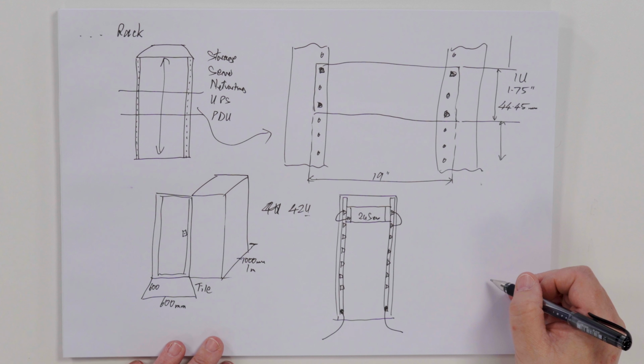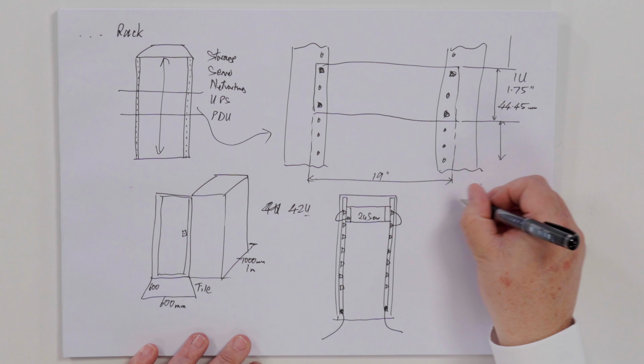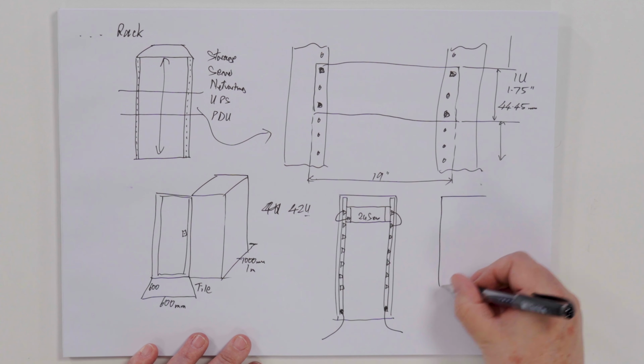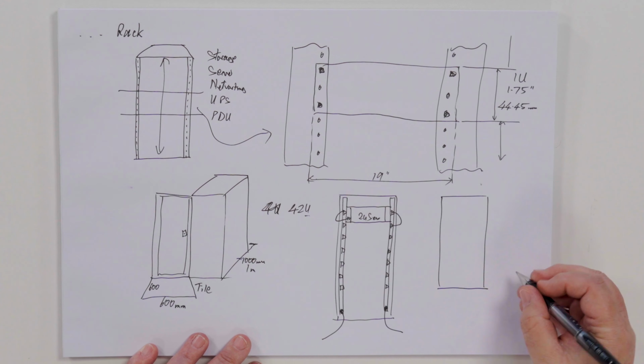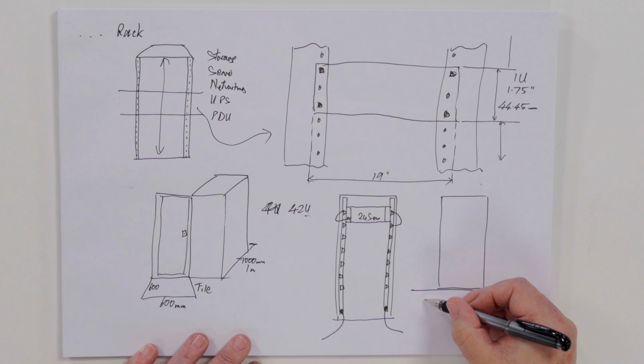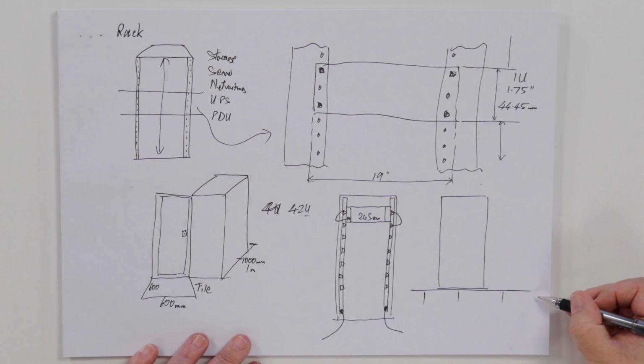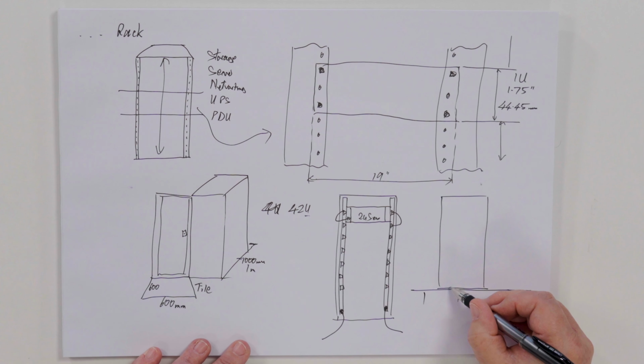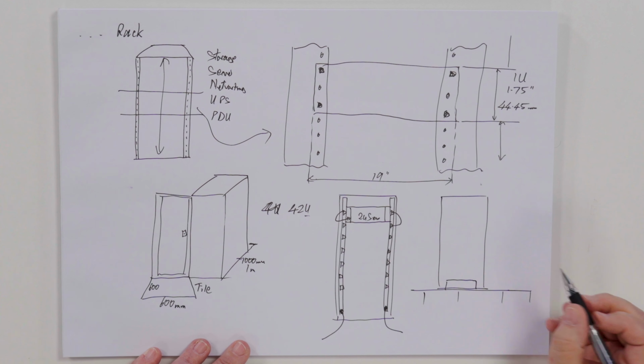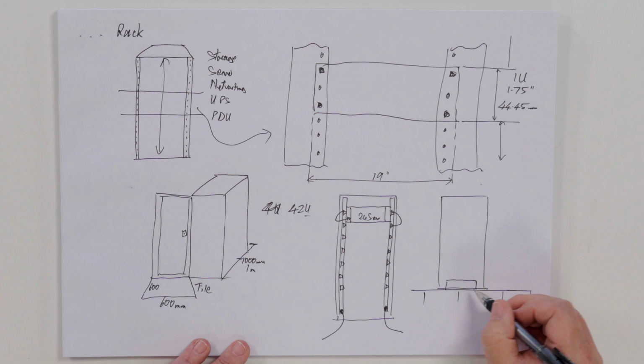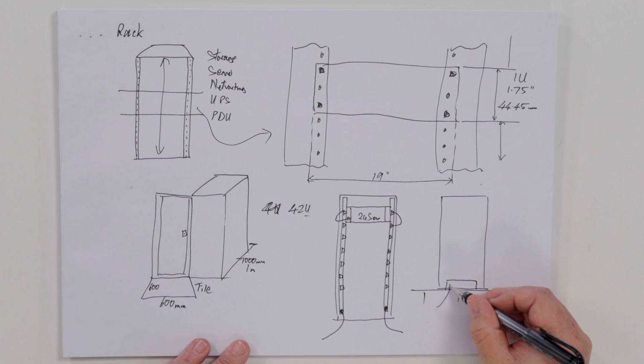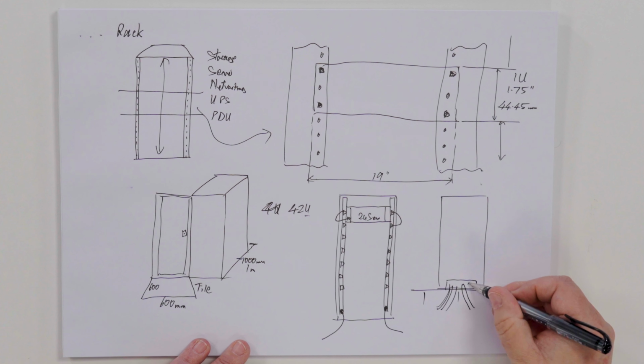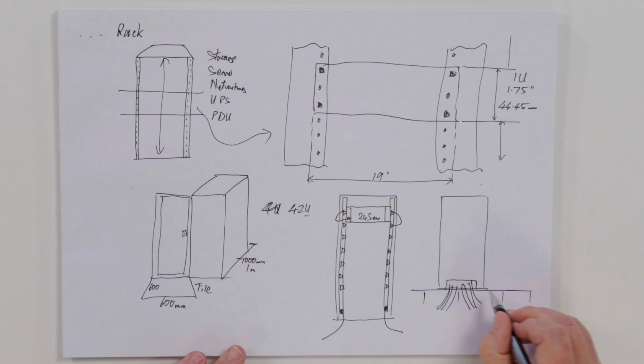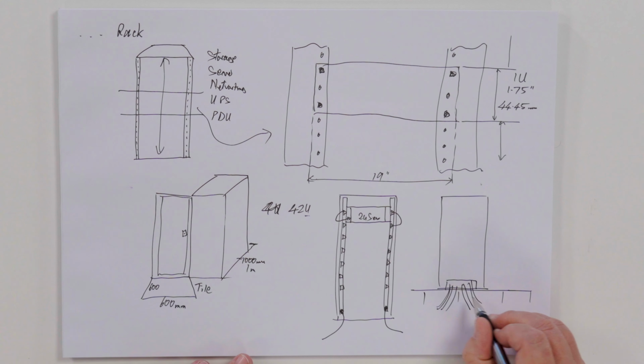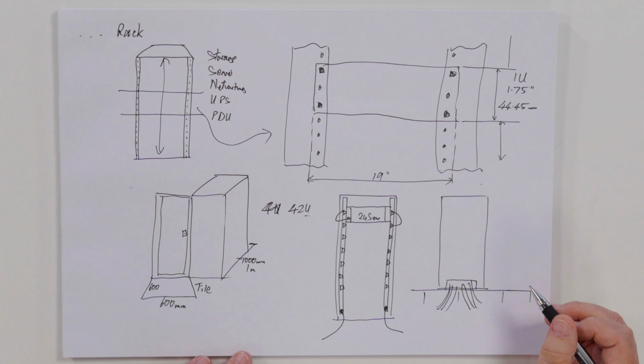The way cables come out of the rack is also interesting. You have a rack that may be sitting on a raised floor, with legs underneath it. At the bottom of the rack you can have a cutout in a floor tile and a cutout in the rack, and all the cables connected to technology in your rack will come out that bottom floor tile and out of the bottom of the rack. That's normally the way you do it on a raised floor.